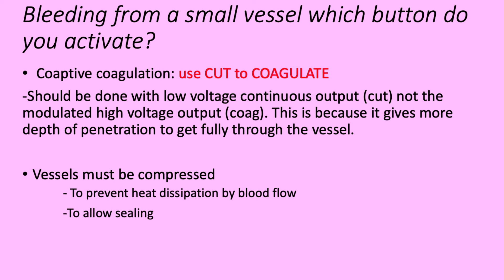Question about coagulating vessels: why do you use the cut mode instead of coagulation for small vessels? For small vessels, you can use cutting because it requires low voltage, reducing the risk of high-frequency current dispersing to the body and causing tissue necrosis. For larger vessels — especially in vascular surgeries — you have to use the coagulation method. Cutting is preferred for small vessels because it requires low voltage, reducing side effects compared to coagulation.